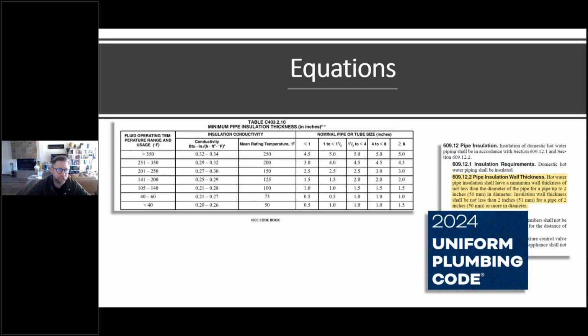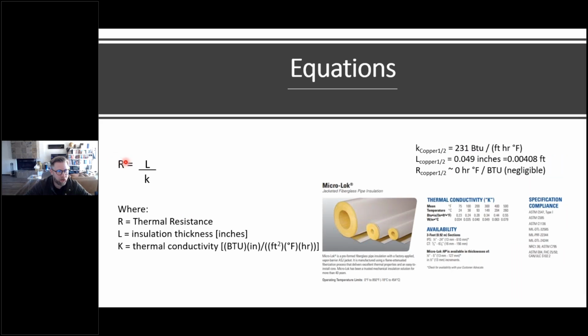Now, the base equation we're going to use, going back to our college days, is thermal resistance equals insulation thickness divided by thermal conductivity. And different materials have different thermal conductivity. Copper, for instance, has an incredibly high thermal conductivity, which means its resistance is low, because thermal conductivity and thermal resistance are inversely proportional. Insulation is the exact opposite. Insulation has a low thermal conductivity or a high thermal resistance.